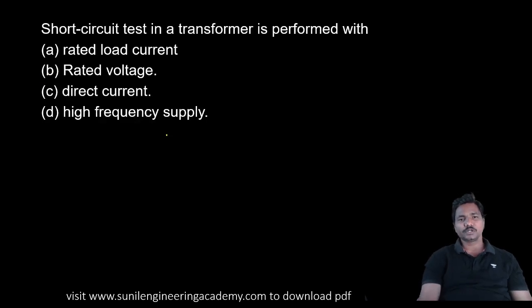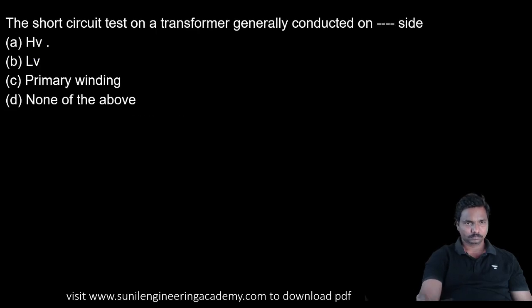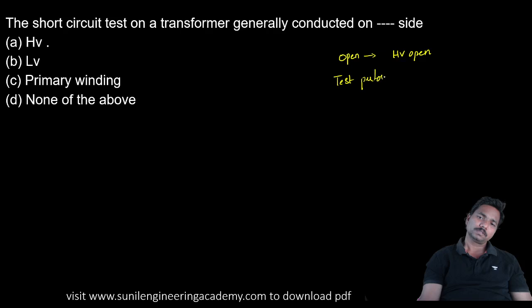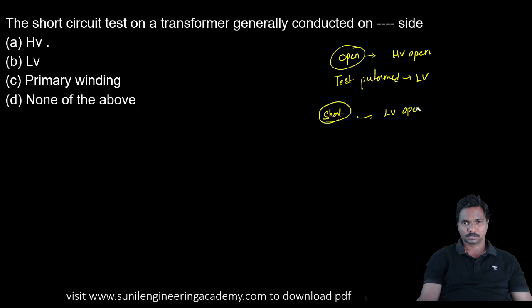Coming to the next one. The short circuit test in a transformer is performed with dash rated current, rated load current. The short circuit test on a transformer is generally conducted on dash side. We have already discussed the open circuit test: HV open, test performed on LV. For the short circuit test, it is reversed. LV is short, test performed on HV. Here they are asking on which side it is conducted, so the test is performed on the HV side.